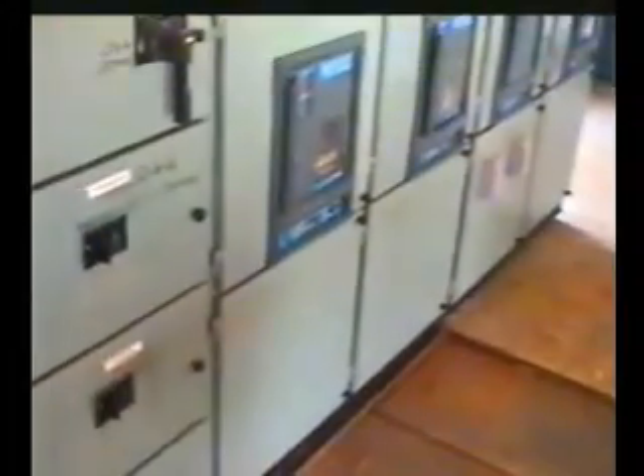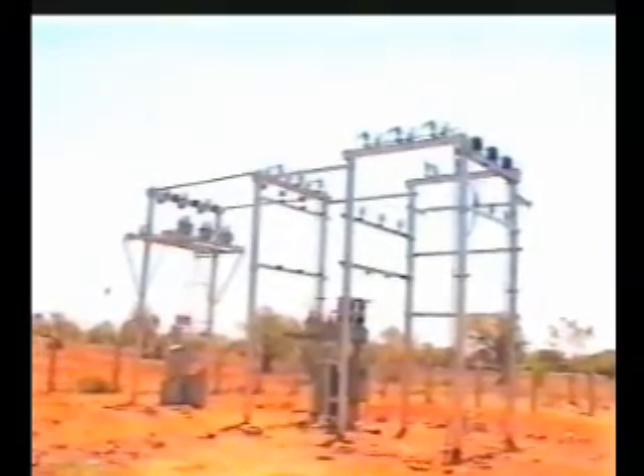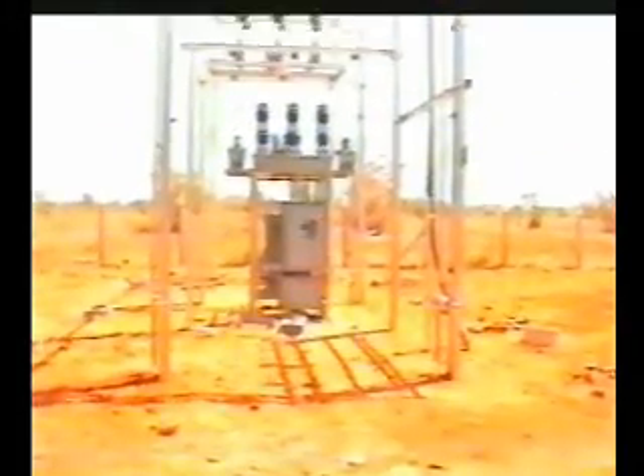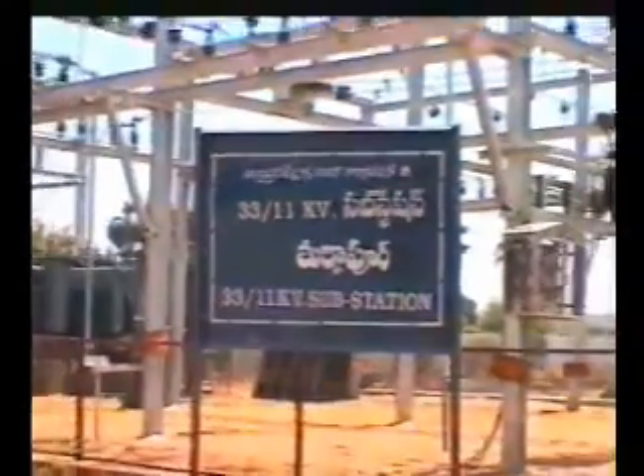This is the individual power distribution panel at 415 volts, with protective and metering instruments. And here is the synchronizing panel with various relays, controllers with load sharing monitors to synchronize the output power with the grid. Now we are in front of the oil-immersed main step-up transformer to step up the voltage from 415 to 11,000 volts. This is to match the grid. Here we have the transformer HT breaker, HT feeder breaker, 11 kV substation with incoming and outgoing feeders, and high tension trivectors. Through these, the power is ultimately exported to the nearest electricity board substation.